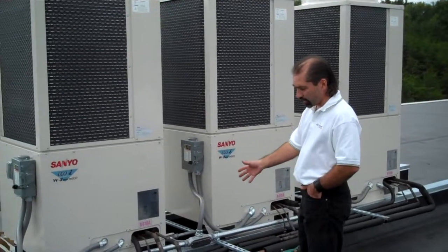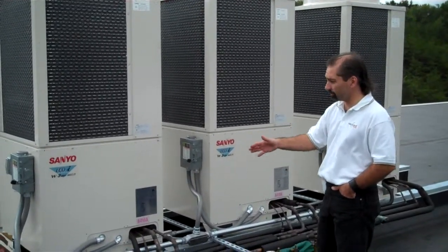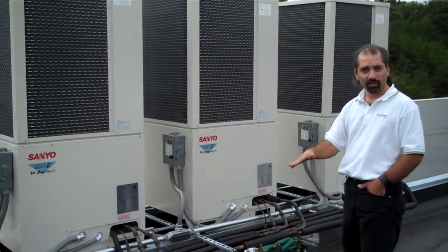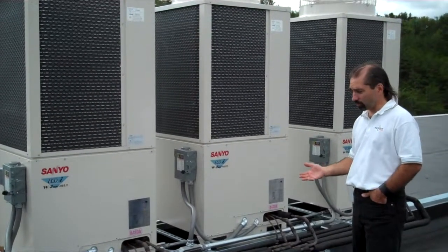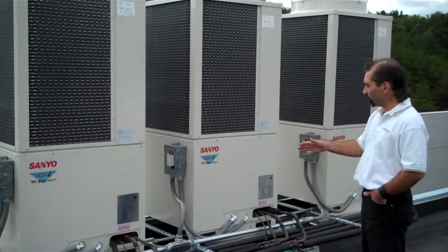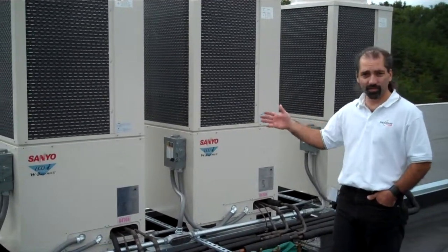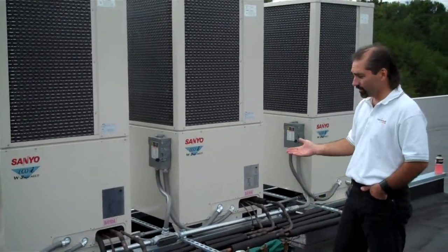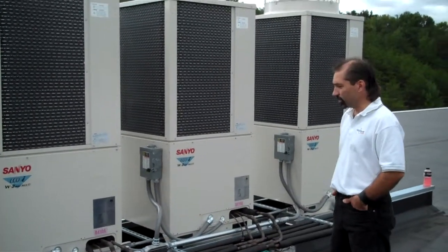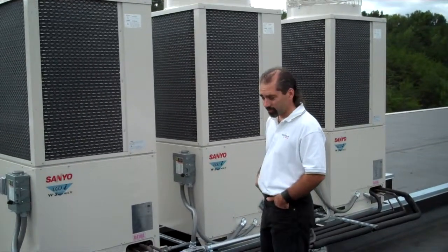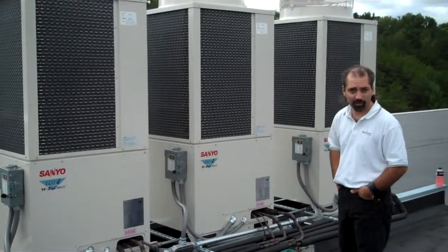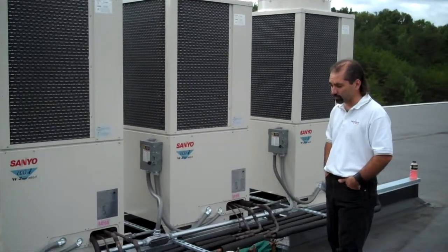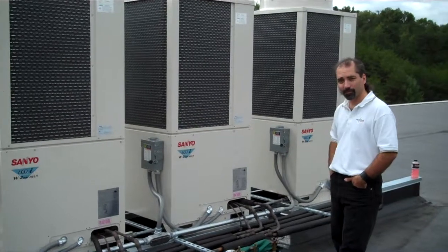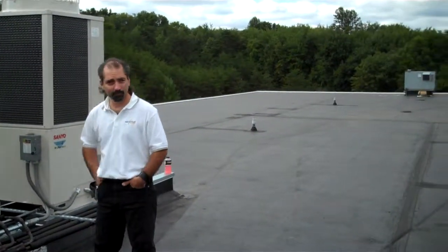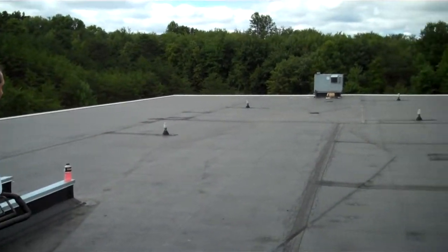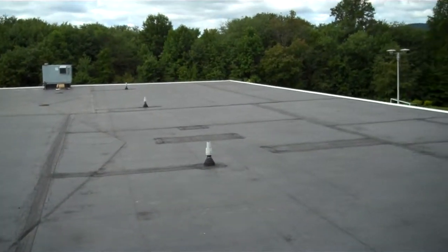So this is a 3-pipe variable refrigerant flow system. So these compressors will ramp up and down depending on the load of the space, which units are calling for heating, which units are calling for cooling. So each one of these systems could be running at 5, 10, 15, 20% depending on the load in the space. So this is all high efficiency? Absolutely. High efficiency, new R410A refrigerant, so it's not the old R-22 that's in typical residential and lighter commercial units. It's all 410A refrigerant. And it looks like there's lots of roof space left and very few roof penetrations that you've had to put in up here to air condition a school.